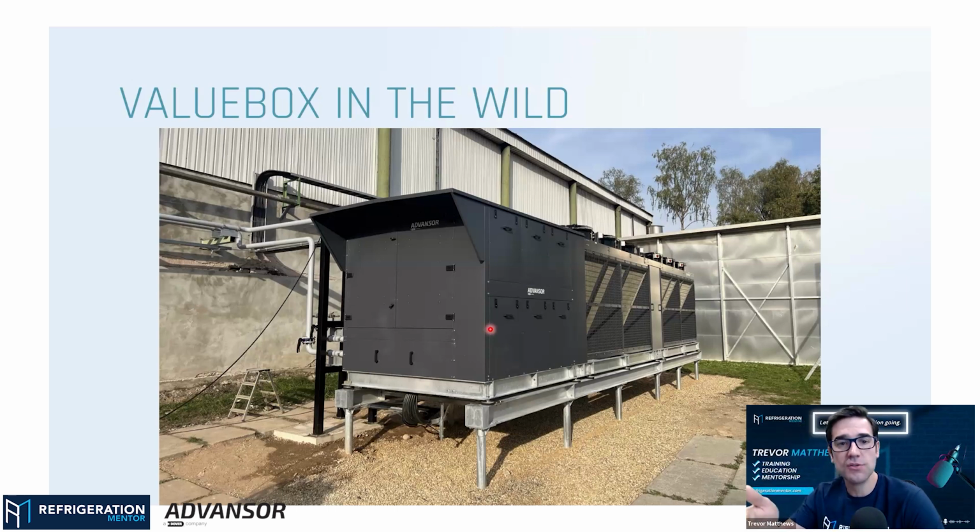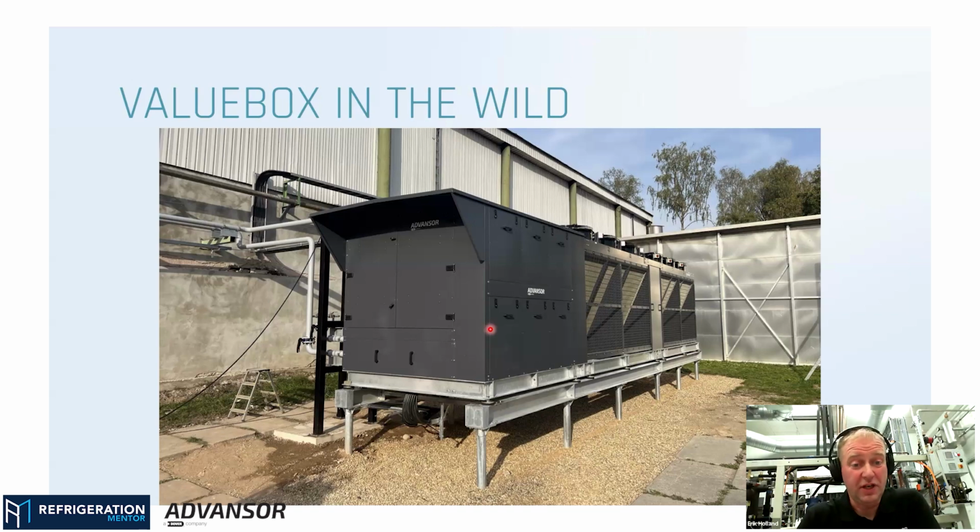So you're getting CO2 in there, you're watching it. What's the next step? Yeah, the next step in this case with the heat pumps, we simply just start at a low capacity. We can control the capacity directly. So how much compressor capacity are you cutting in? We start at low levels just to make sure everything's working, and slowly get the system working, checking all your water temperatures and your evaporator temperatures, that all the figures check out.